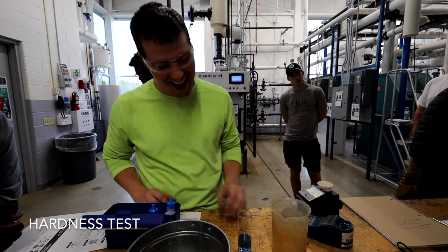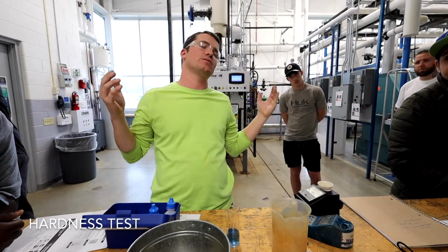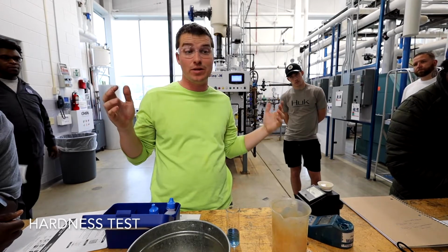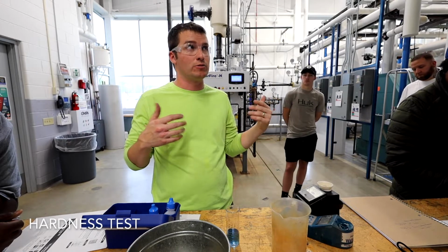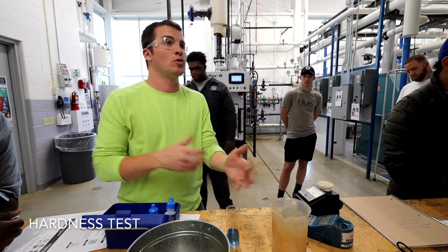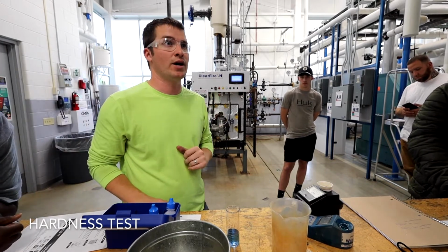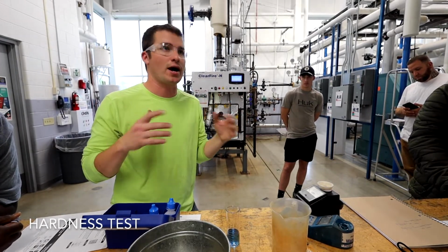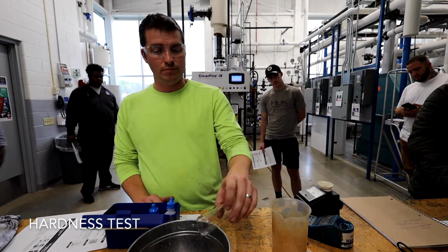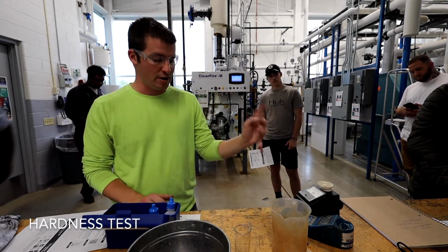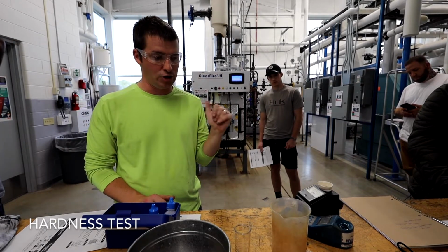Okay, interesting. So, and again, maybe it's just, hey, it's 50 years old, I had a failure, it is what it is, right? Or maybe it's like, no, something's wrong, one way or the other, right? And there was a premature failure because we didn't have good water treatment in place, or whatever. You superheated it on accident, right? And you caused it to crack, or whatever the case. It could be a number of things, right? So, okay. So we know we're gonna have to validate in our condensate and in our softener if we're getting hardness or not to try to determine what the problem is.